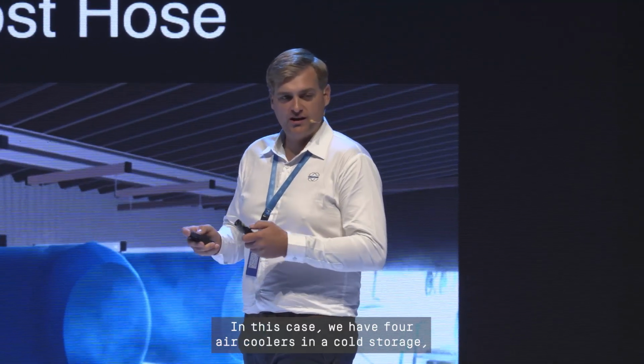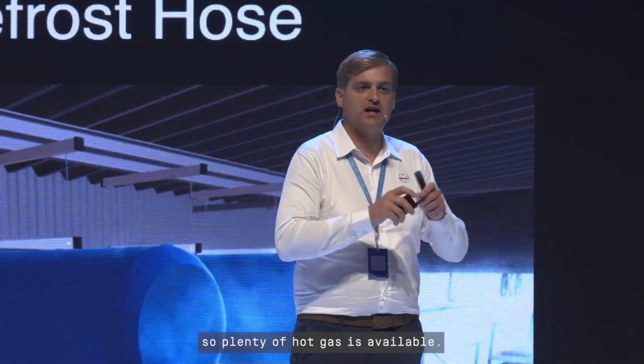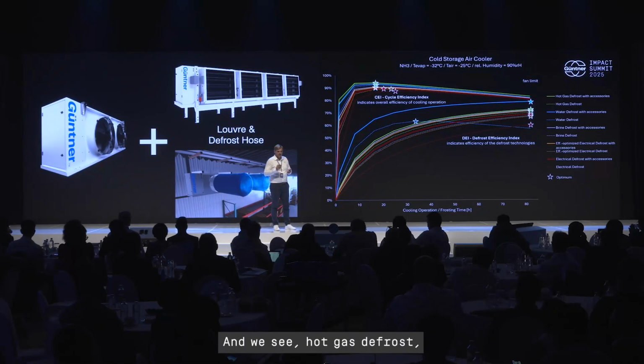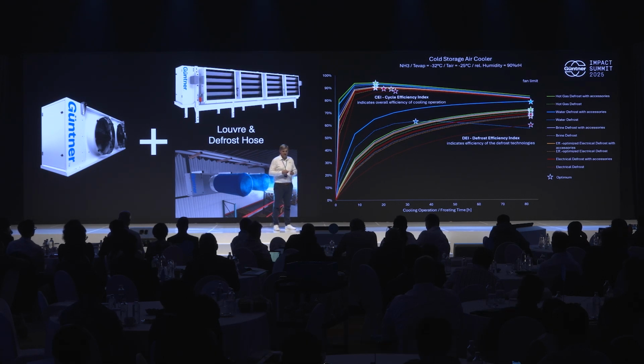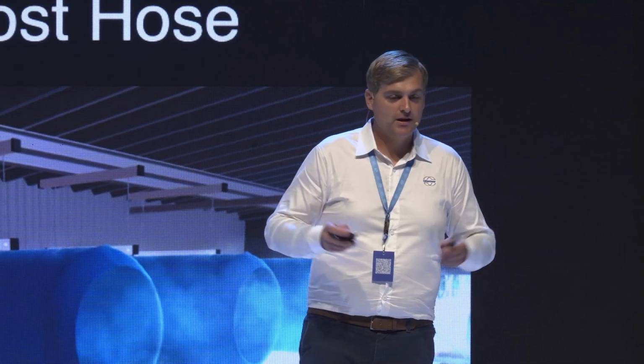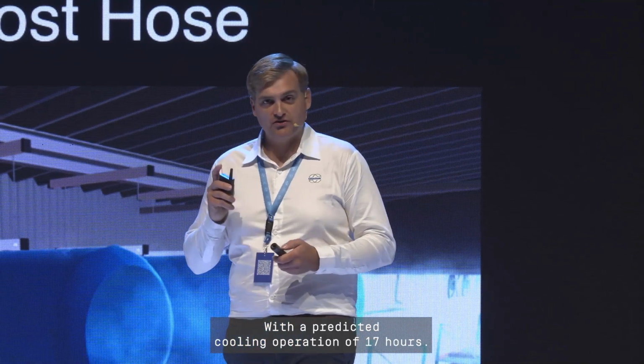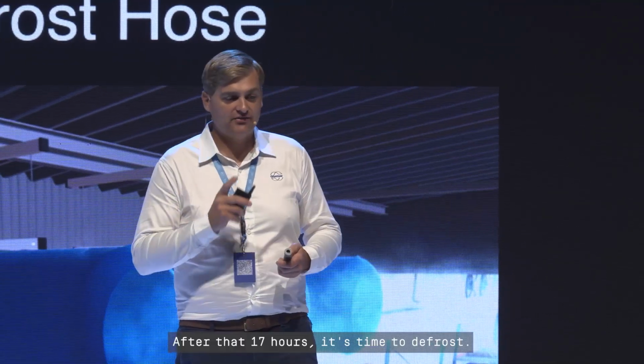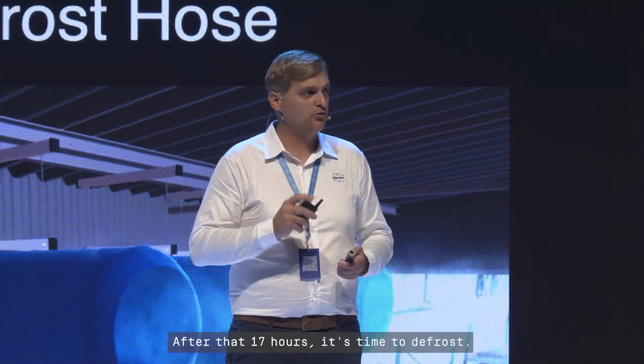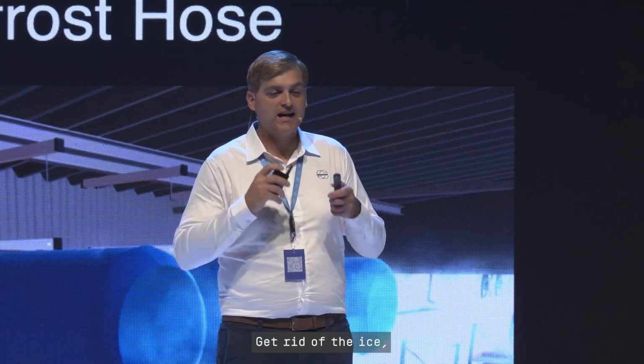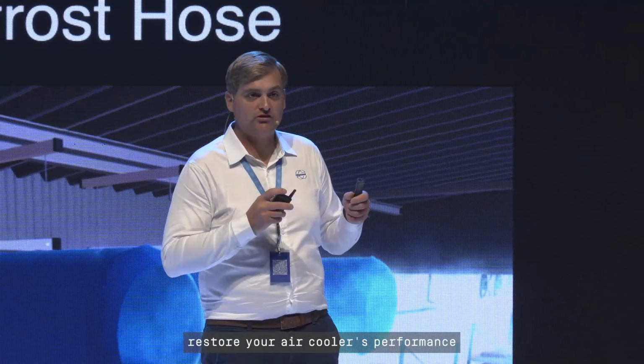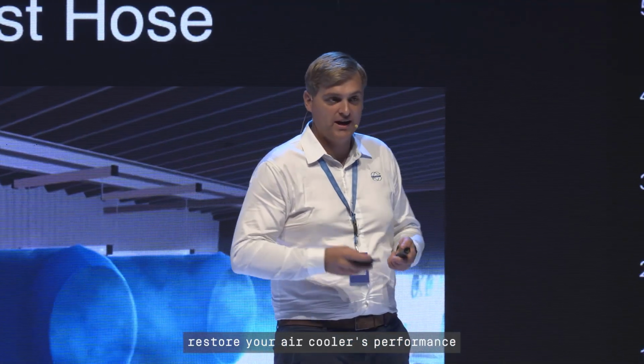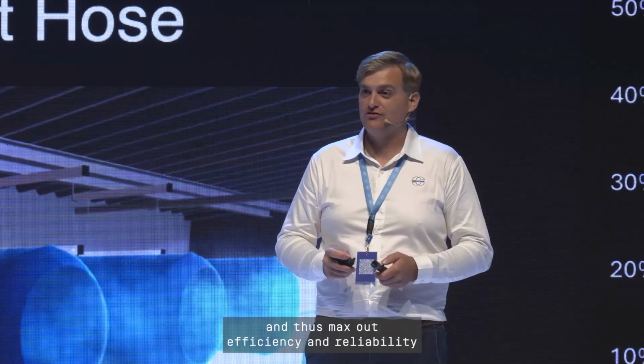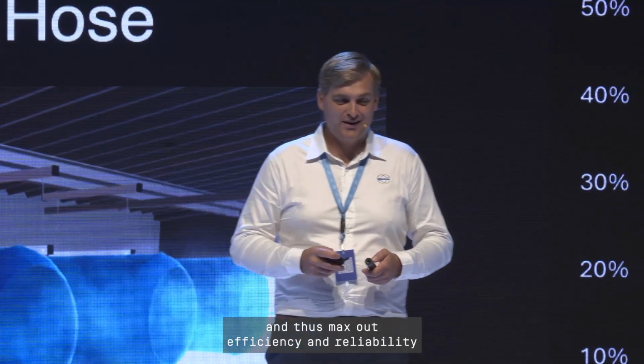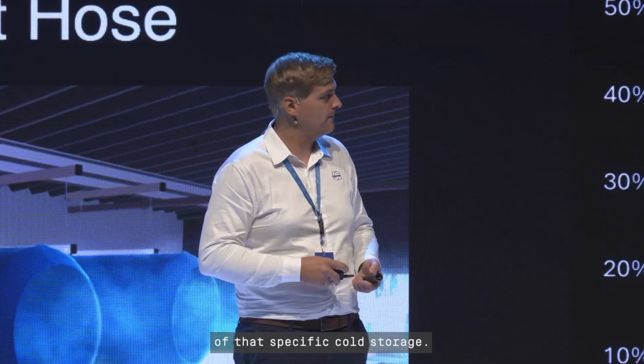In this case, we have 4 air coolers in a cold storage, so plenty of hot gas is available. And we see hot gas defrost, the green line on the very top, is the perfect solution, with a predicted cooling operation of 17 hours. After that 17 hours, it's time to defrost. Get rid of the ice. Restore your air cooler's performance and thus max out efficiency and reliability of that specific cold storage.